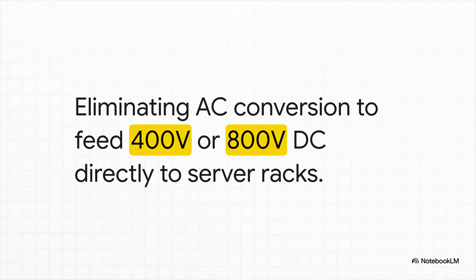Hyperscale AI is literally forcing the industry to completely ditch traditional AC networks inside the data hall. Converting AC to DC at every single server rack just creates way too much heat and wastes a ton of space. So instead, the facility converts the power centrally and feeds 400 volt or 800 volt DC directly to the server racks. It's a massive leap forward, completely driven by the extreme needs of AI hardware.